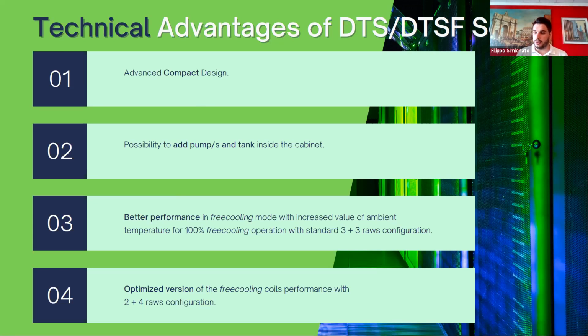Of course, depending on the performance that the customer asks, we can also follow different fields with this configuration. So if the customer is looking for an efficient solution, looking at parameters like SEPR, we can move to different kinds of configuration for the condenser coil. So we can move with a 4+2 rows configuration, 4 rows on the condenser coil and 2 rows on the free cooling, or the standard configuration working 100% free cooling, giving more importance to the free cooling side with a 3+3 row configuration, or the optimized version of the free cooling, the 2+4 rows configuration.